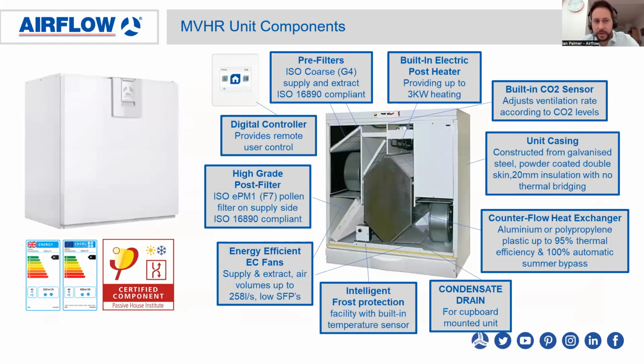This is an anatomy of a heat recovery unit. On the left there, you've got what the unit looks like when it's all closed up, just like a standard white goods appliance to go in the home. These can be installed anywhere in the home, ideally in the heated envelope of the building, in the utility room. The middle image here shows you the inside of the unit.